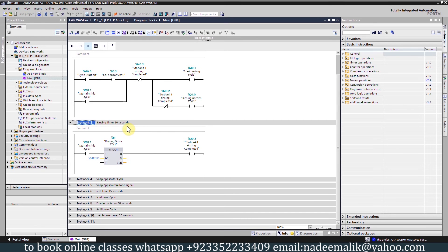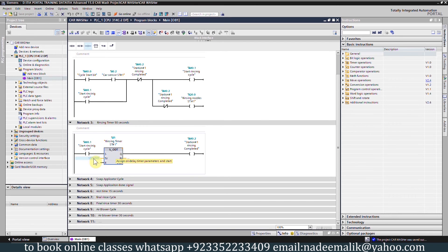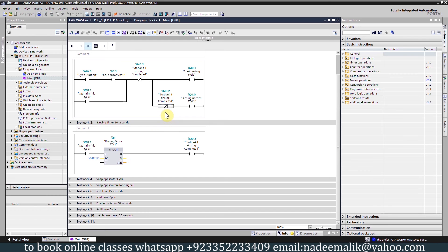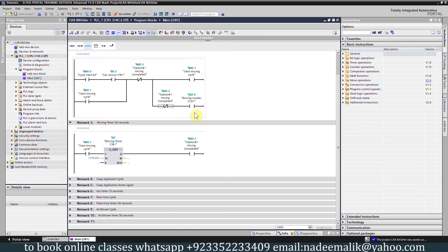In network number 3 we have a rinsing timer. When bit M0.1 start rinsing cycle is on, it will start timer T1. Once the 50 seconds are over it will turn on the station number 1 rinsing completed bit M0.2. We have inserted a normally-closed contact of M0.2 here, so once the 50 seconds are over this contact opens, turning off output Q0.0 and closing the rinsing nozzles.